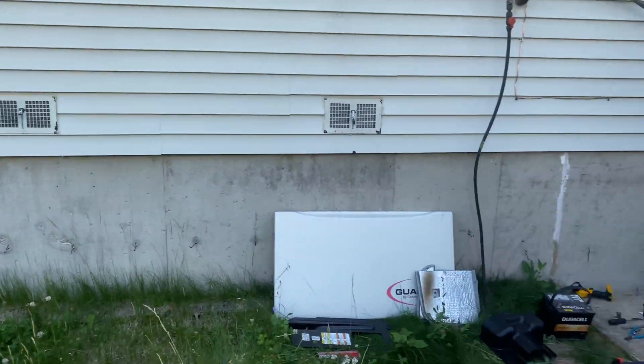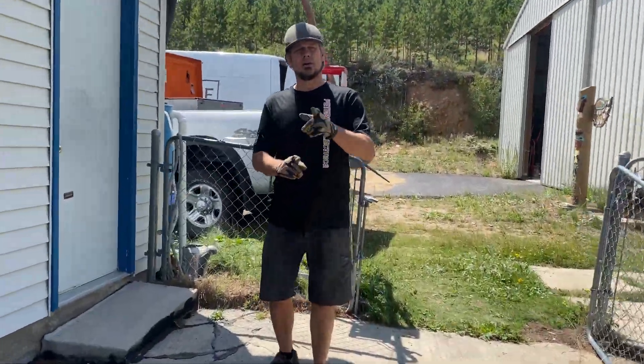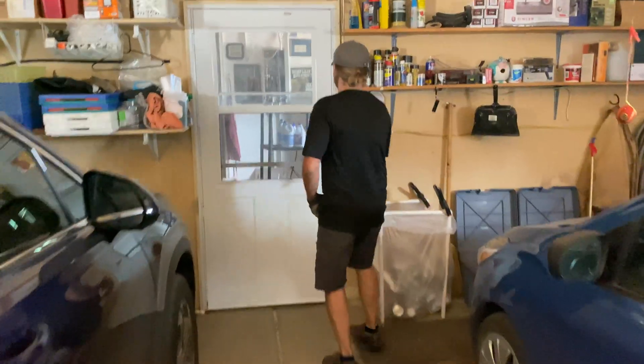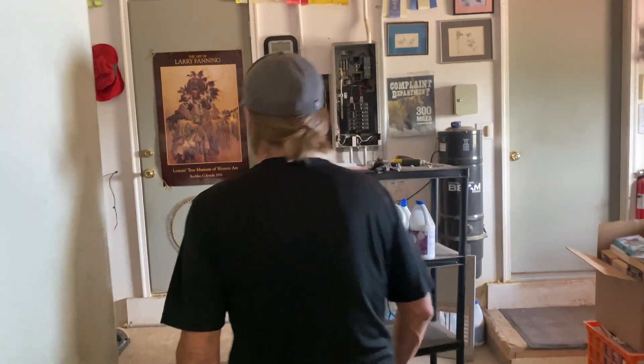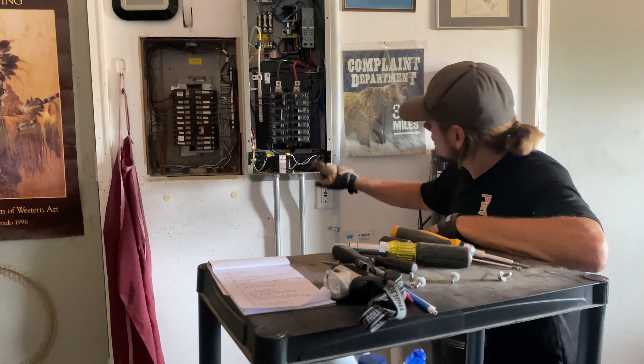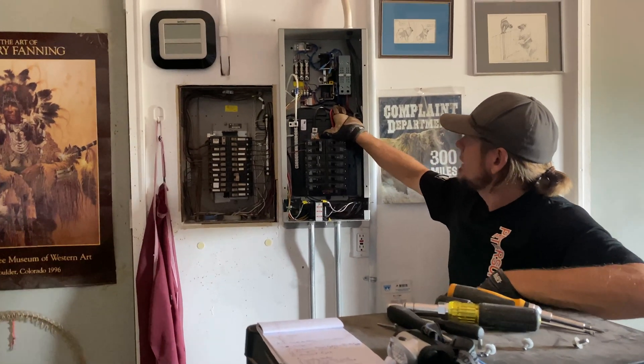We had to check if the feeder wire was grounded out to the neutral and melted in the conduit. That Generac comes into here to the contactor when it senses that the solar goes out.